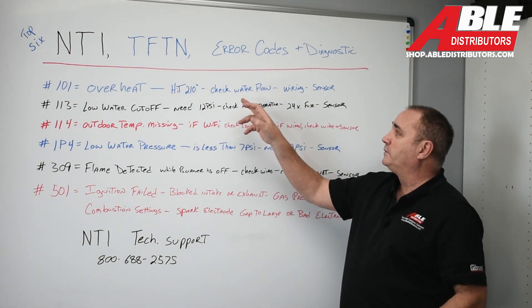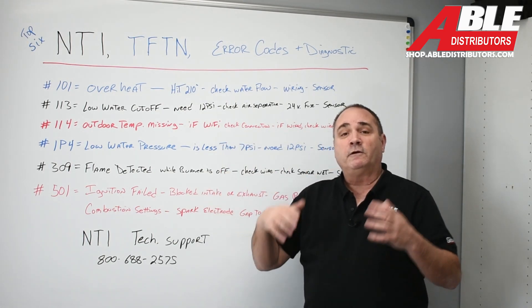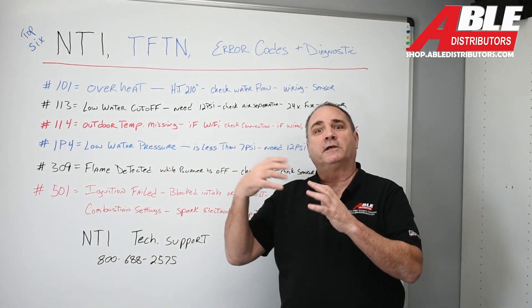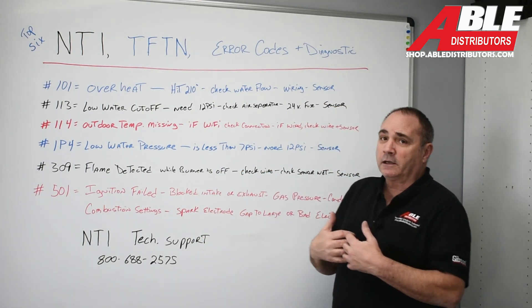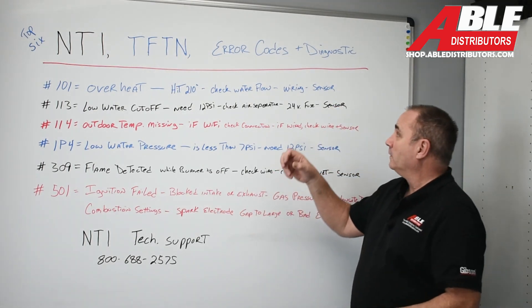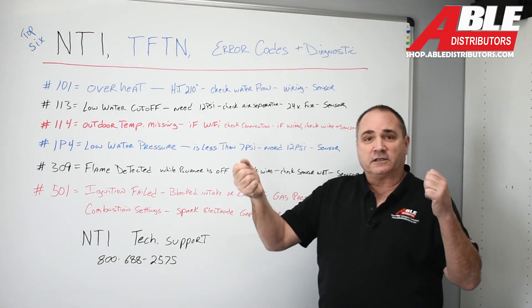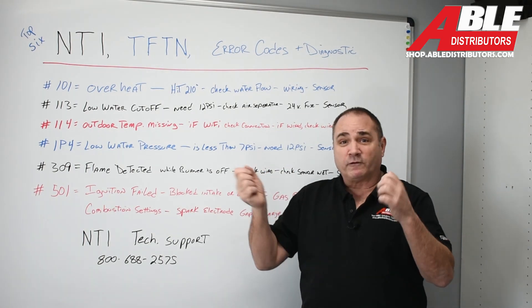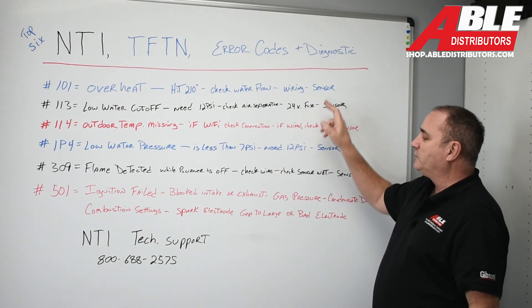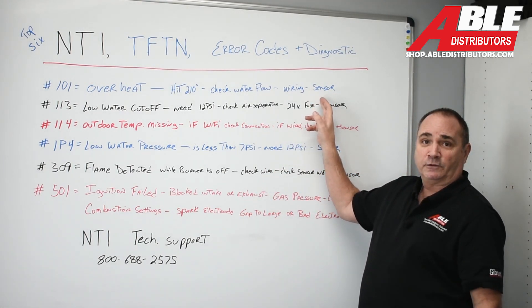The things you want to check: check that boiler pump, make sure it's working. If you have a Y strainer ahead of the return side, make sure it's clean. Whatever you have going on, make sure you've got plenty of flow through that boiler. Then check the wiring to the sensors — make sure nothing came off, fell off, or vibrated off. Last but not least, you might call tech support and check the actual sensor.